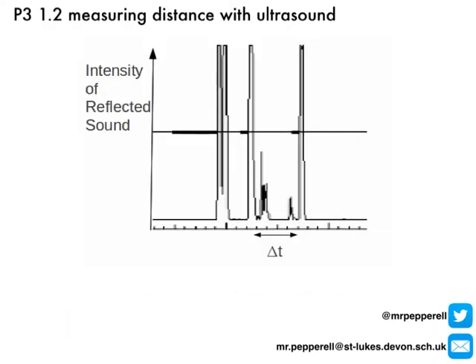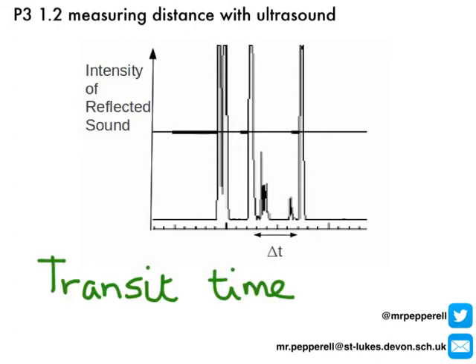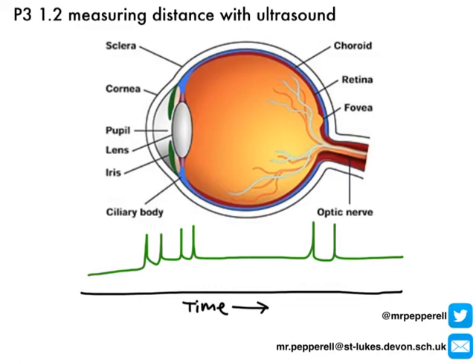What we actually see from an A-scan is one of these plots. The peaks on my plot, which you can see going up here, represent the partial reflection of the ultrasound wave being detected by the transducer. And along the bottom, we have the amount of time they took to reflect, shown in seconds. The time it takes for each pulse to be reflected back is what we call the transit time.